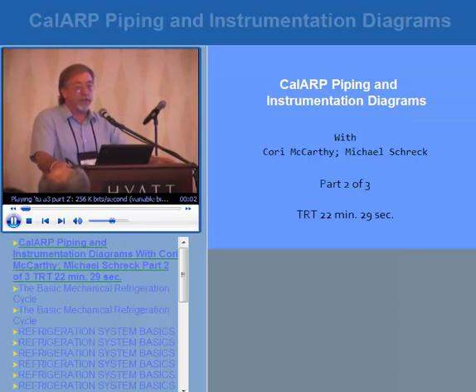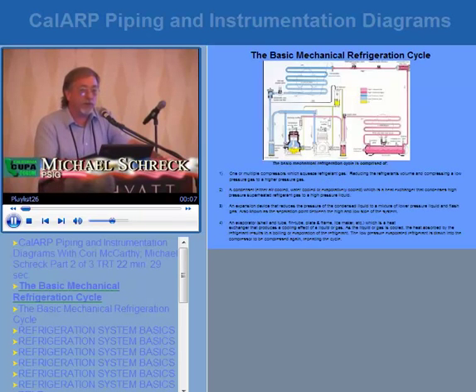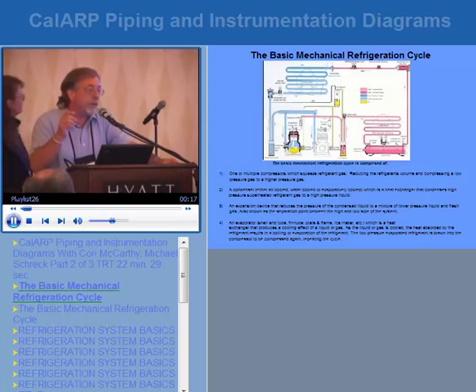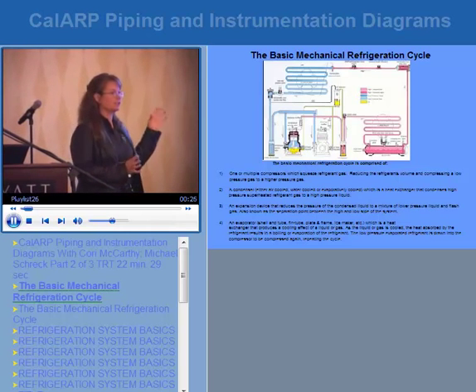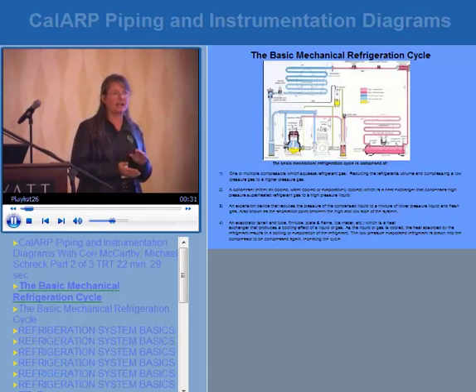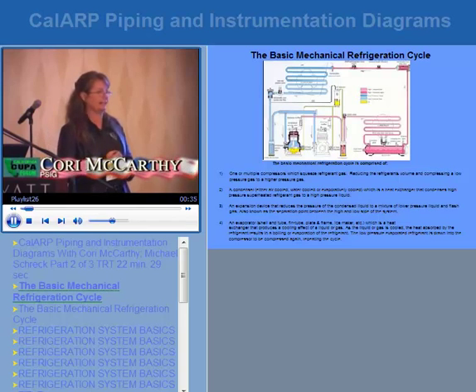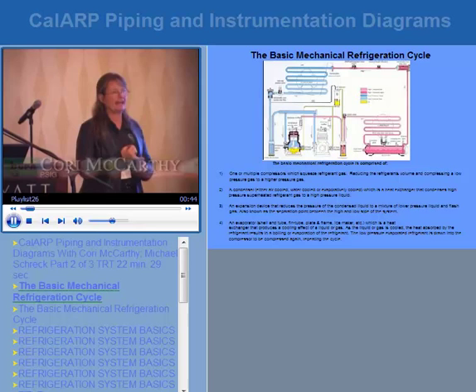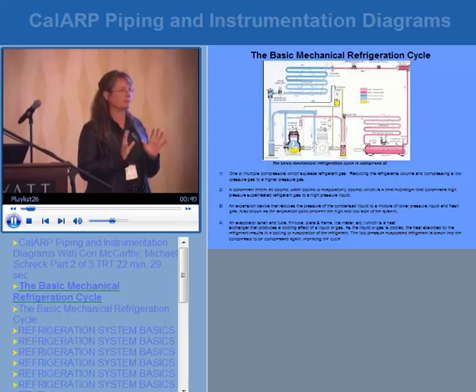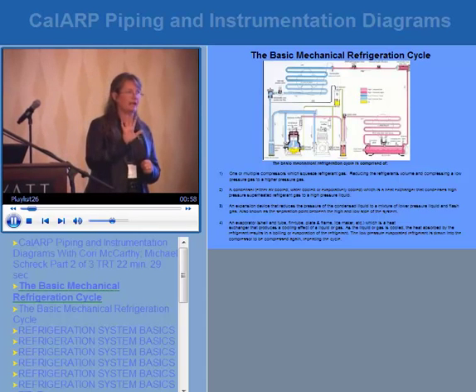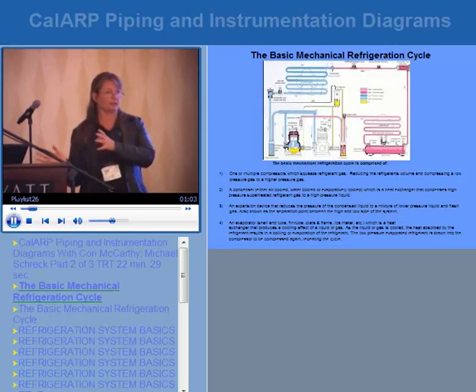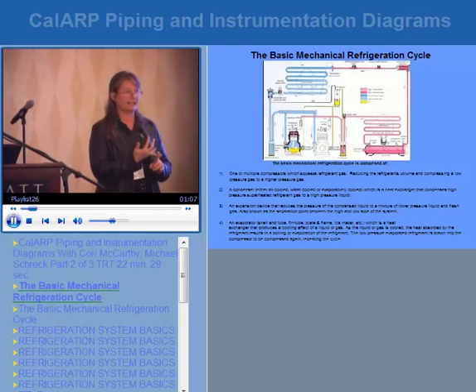To understand P&IDs, you have to understand the basic refrigeration system and what the components look like. One of the most common findings is that P&IDs have not been updated. A simple check is to look at the types and quantities of equipment. When preparing for a site visit, request a copy of their P&IDs a week after your letter. In the three weeks you prepare, count the major components: compressors, condensers, evaporators, pressure vessels, and pumps.